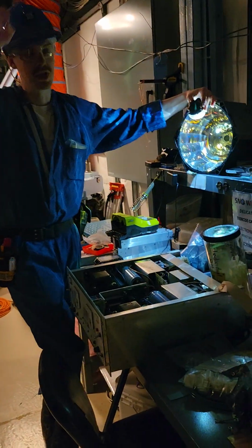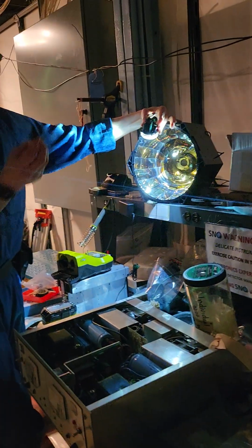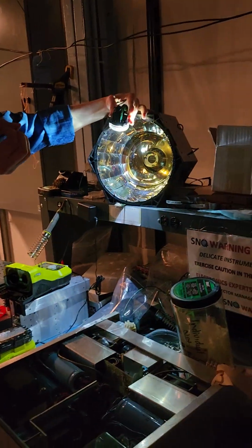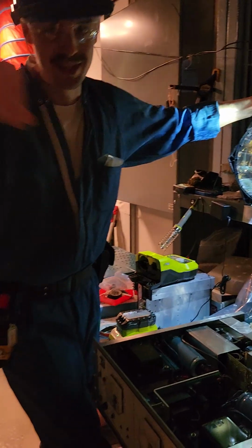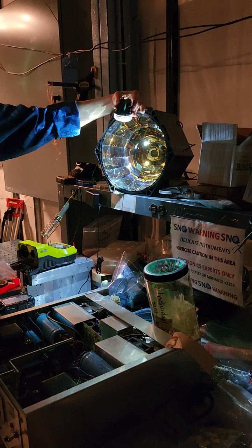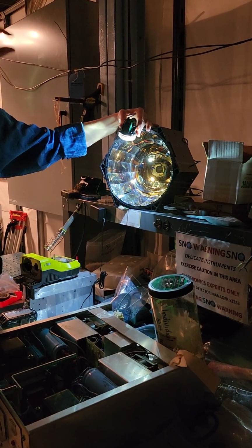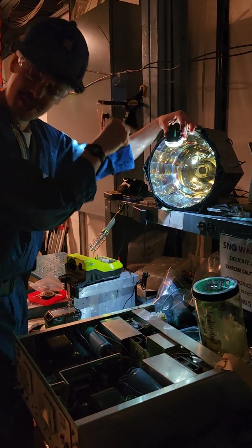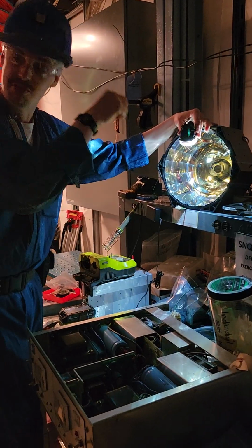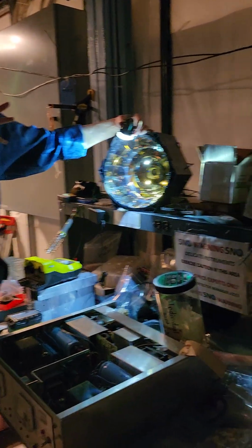Each of these dynodes, held at a different potential, essentially attracts that electron. So you get one electron, it hits the first stage dynode, and that knocks out 2 electrons. Then those 2 electrons go to the next one, and it's exponential. If you have 10 or so dynodes, you end up with 2 to the 10th. So you end up with this huge charge avalanche hitting your anode, and that produces a charge pulse. That pulse signal is also proportional to the incident photon. If you have a higher energy photon, you get a larger peak, and you can do some analysis on it. We don't really.